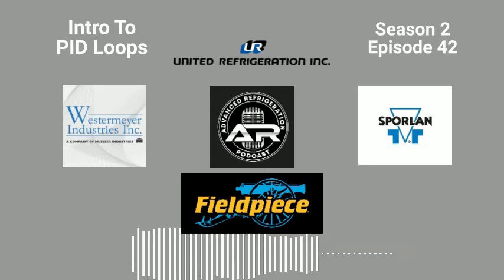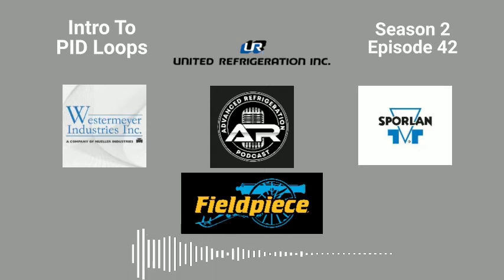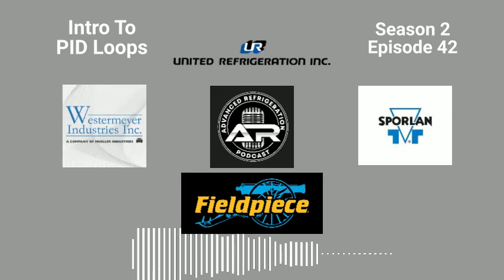Where you would have these peaks and valleys with the P loop, you want to try to get the peaks and valleys as low as you can before you start adding I. Once you start introducing I gain into the actual algorithm, that's going to start bringing you to where you're barely overshooting or not overshooting at all, or undershooting. That I value adds to that loop over time. Now, with that being said, the D value, I don't have a lot of experience adding the D in there because we don't really use it that much.